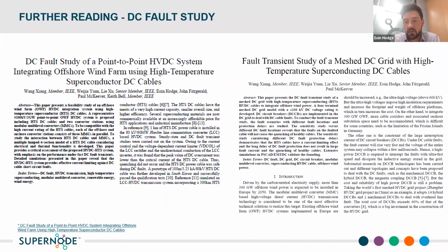The next study, an extension of the first one into meshed grids, has been approved for publication quite recently in the IEEE Journal on Power Transactions. So we looked at the operational advantages of a meshed DC grid comprising our superconducting cable technology, and essentially found similar benefits could be accrued. A key benefit is fault protection and power dispatch management when there is a fault on the system.